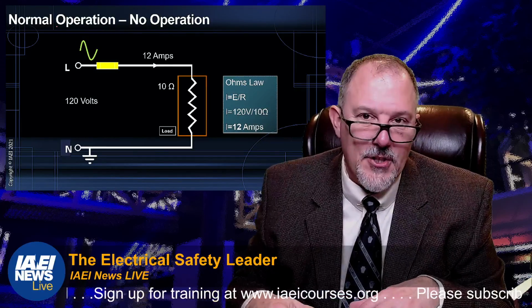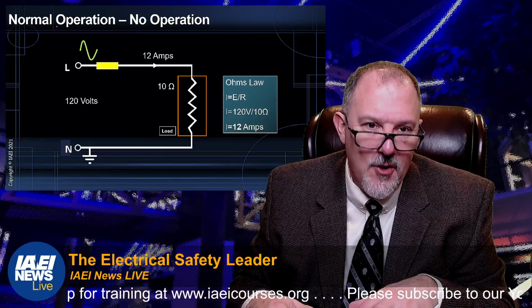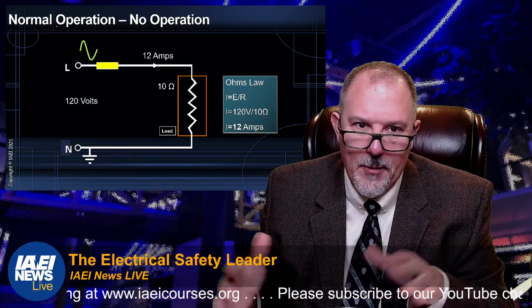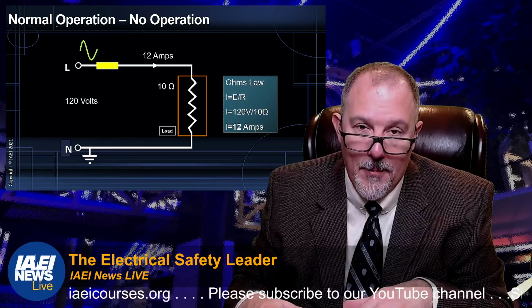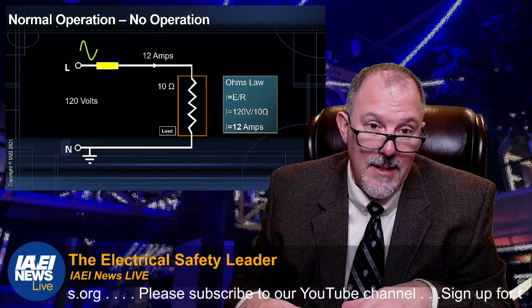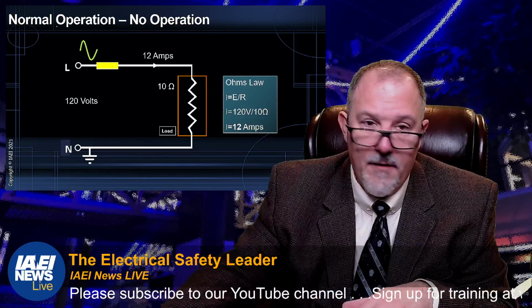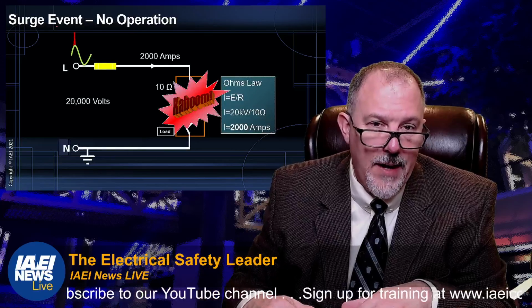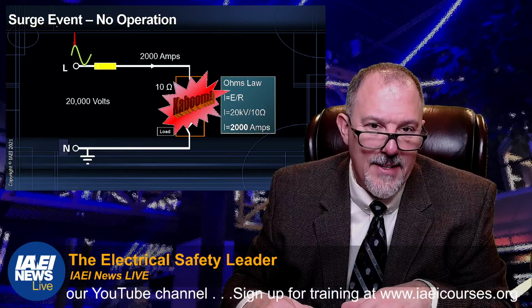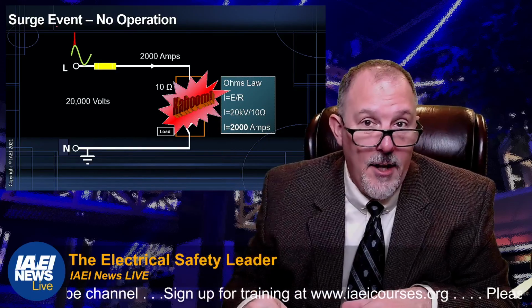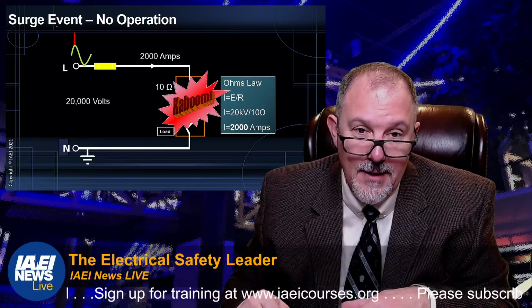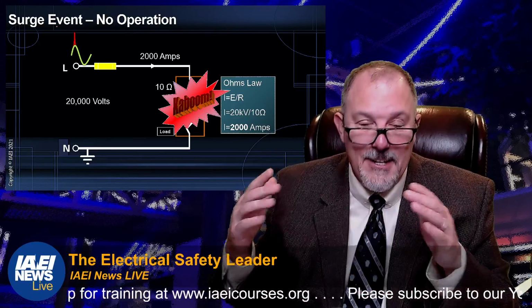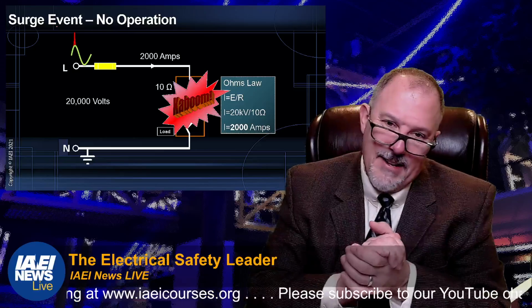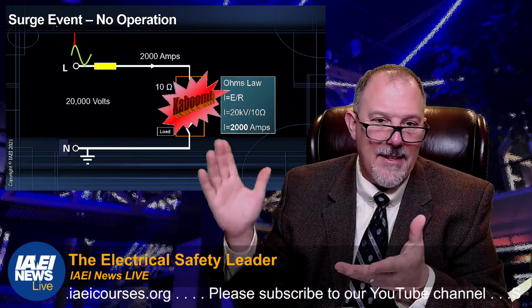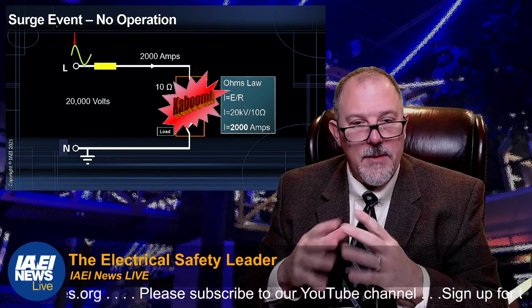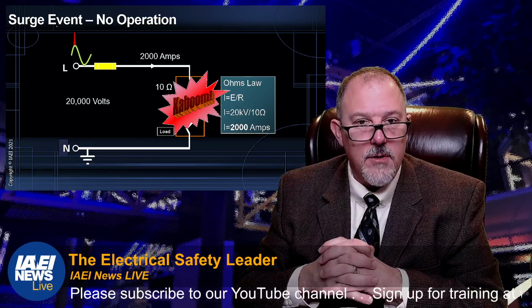I don't know. This is just an example. So if I have a normal operation, I've got a voltage sine wave operating and behaving itself. I don't have any operation of the transient device. But if I do have a transient event, I could have a kaboom. And you've got to love the kaboom, right? That's that. Now we say kaboom. And this is, I love and I hate this slide. I love and I hate both these slides. Because the reason is that a transient event may not result in a kaboom.